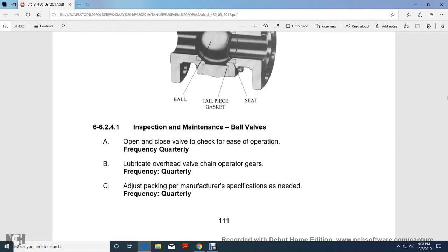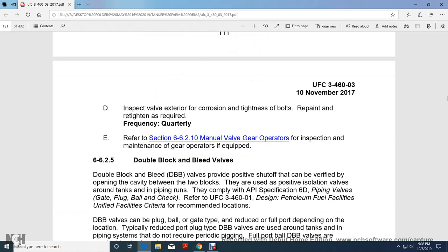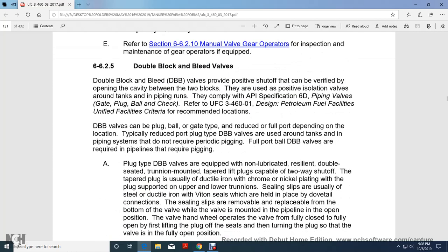Inspection and maintenance of ball valves: open and close the valve, check the ease of operation, frequency quarterly. Lubricate the valve gears quarterly. Adjust packing per manufacturer specification quarterly. Inspect the valve exterior for corrosion and tightness of bolts, repaint and retighten quarterly. Refer to 66210, manual valve gear operators, for inspection and maintenance of the gear operators, if equipped.